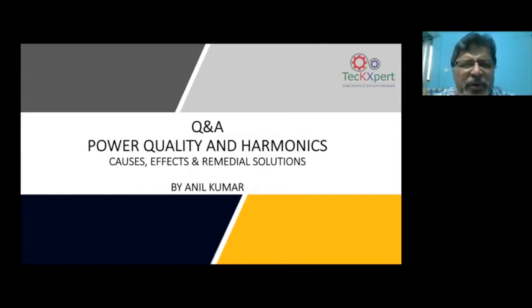Yeah. So my point here is that one thing you can do is check the rated current of the reactor from the nameplate details. That is one aspect. The second aspect is to see what variable frequency drives and other non-linear loads are in the plant, and whether these non-linear loads are causing any resonance. The third is where this capacitor bank is installed in the plant. These are all basically a plant study, and looking at the problem can easily give a solution. I'm sure it is either due to a resonance problem or due to a sizing problem.